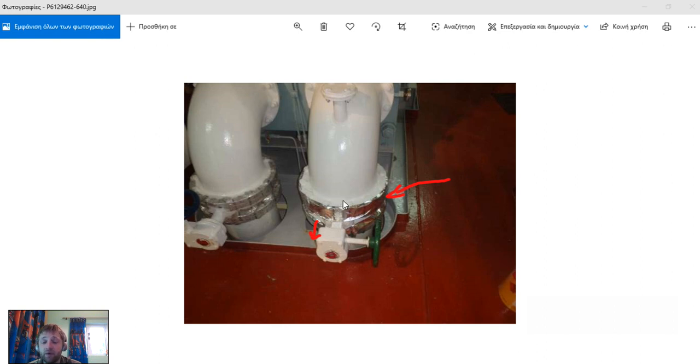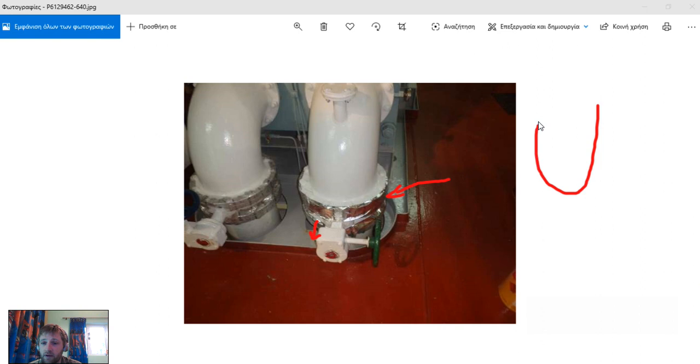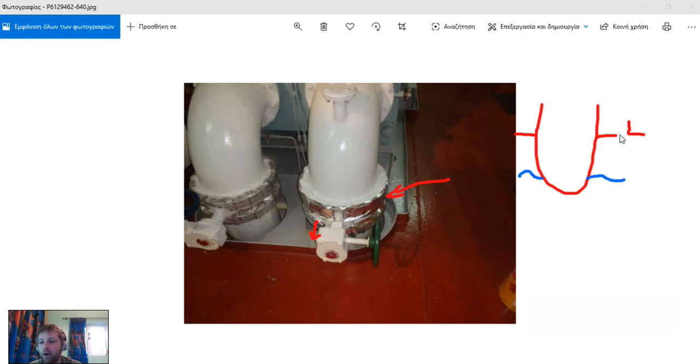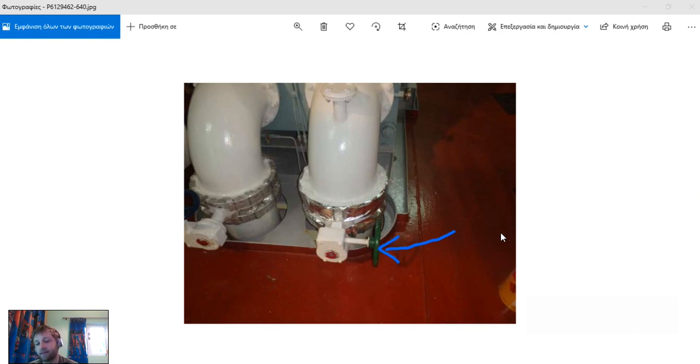After that, if you have leakages observed here, that means your sacrifice flange must be replaced. The best place to replace that one is when you're standing still on anchorage and the ship is in ballast condition. Because as you see, if you are in ballast condition, this height will be reduced, so the pressure that you will receive here in case your valves have a small leakage will be less and you will be more safe to work.